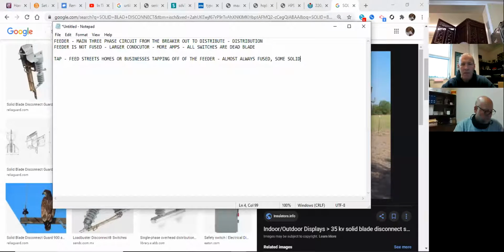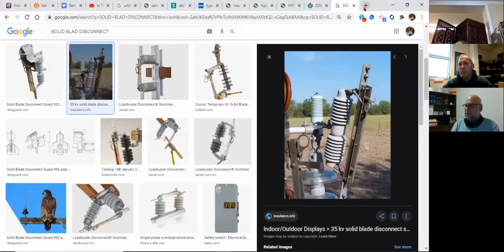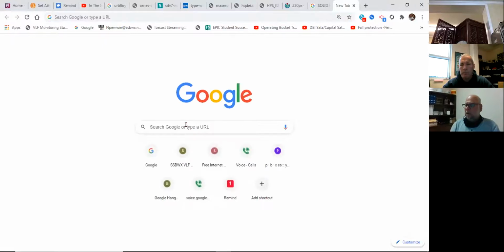So a good definition for a tap: feeds streets, homes, or businesses, tapping off the feeder, almost always fused, some solid. Even in a good portion of cases, Professor V, you could chime in on this as far as Duke is concerned, they're going back to some of these old timey solid taps and putting fuses in them, installing a switch and a fuse in there. What are they doing at Duke? Yeah, same thing. I can think of a time when I started with the company and we had a big section of line that kept locking out in the summer. It turned out to be one tap that was solid, wasn't fused, that was taking it out. So yeah, they're going through and putting fuses on all the taps. It just makes it easier to determine what you've got out. Right, okay, so that's the definition of a tap.